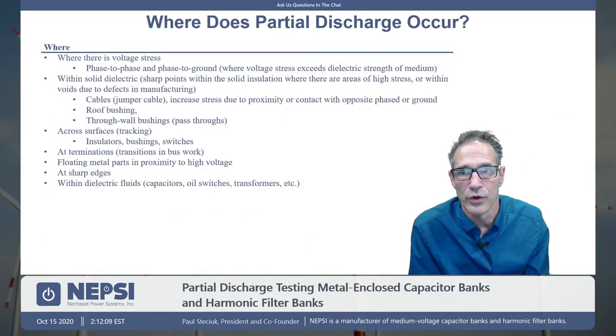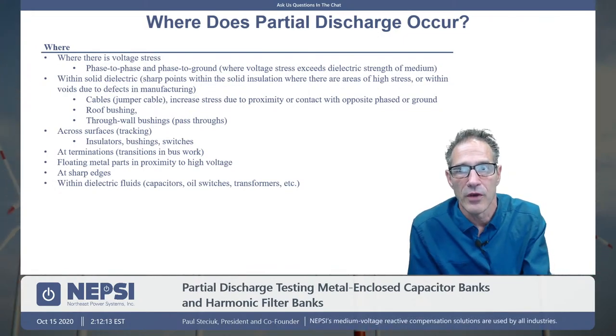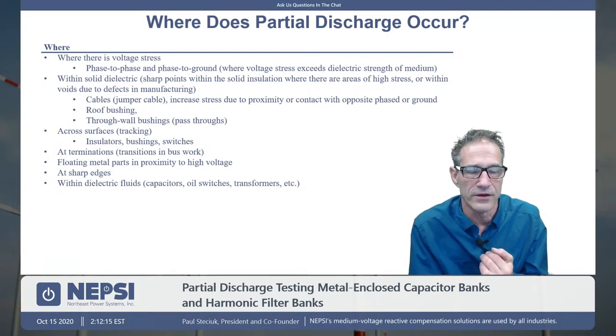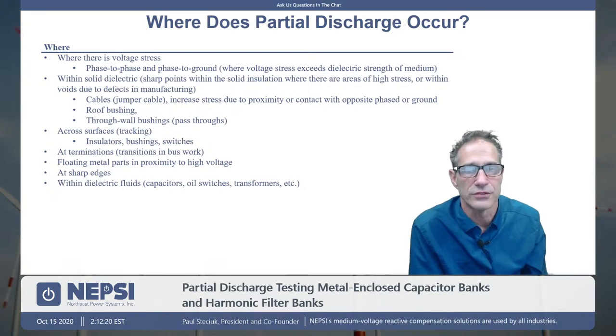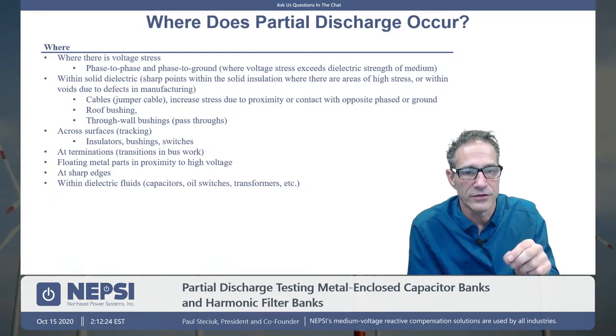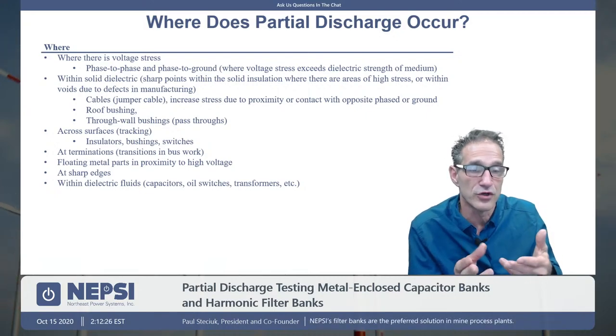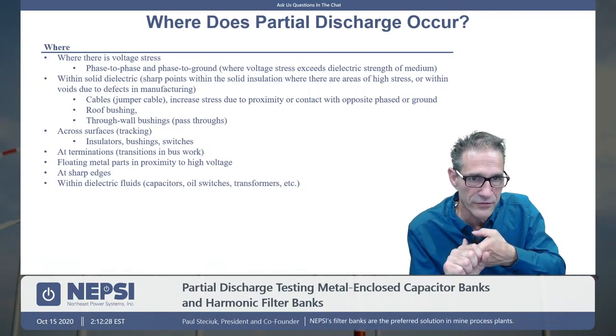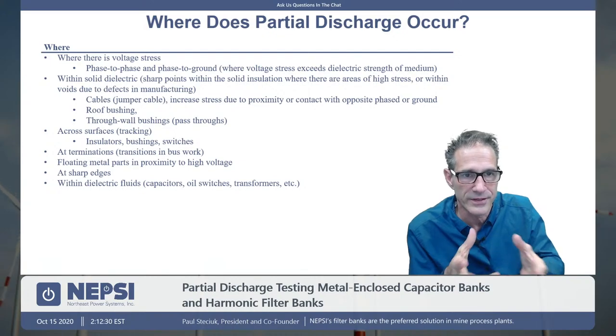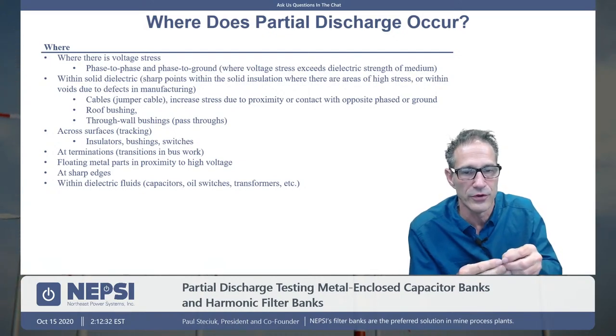So where does partial discharge occur? It can occur in a lot of different places, but generally it's occurring phase to phase, and it's also occurring phase to ground, where you have a significant amount of voltage stress within the equipment. It can occur within solid dielectrics. Say you have a transformer and it's a cast type transformer, sharp points within the actual insulation itself could result in partial discharge at those points.